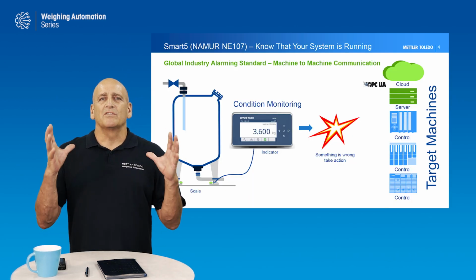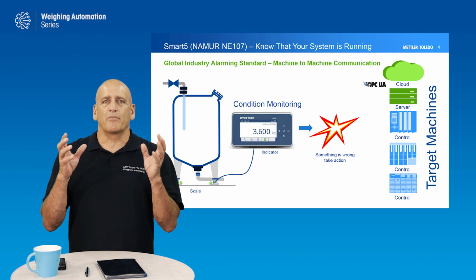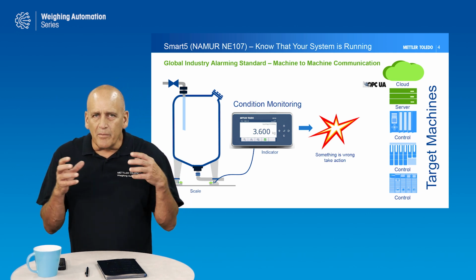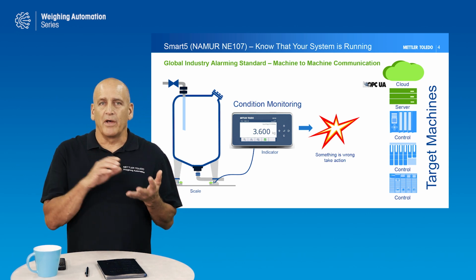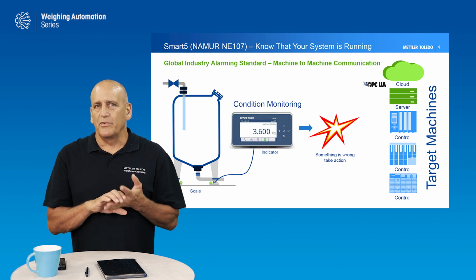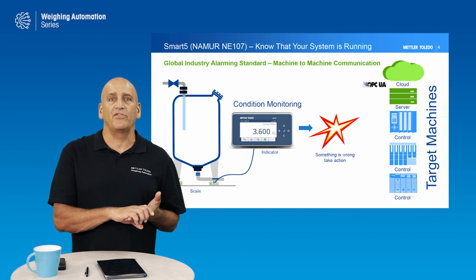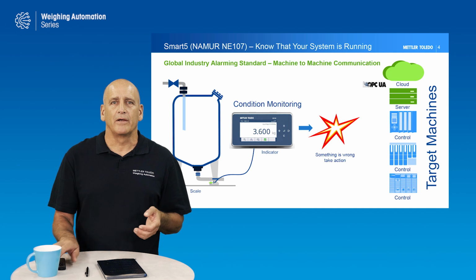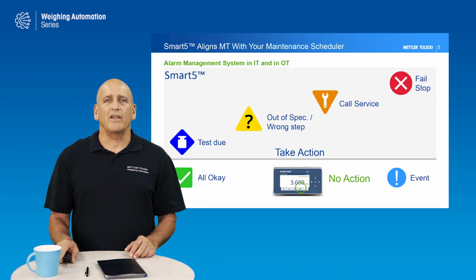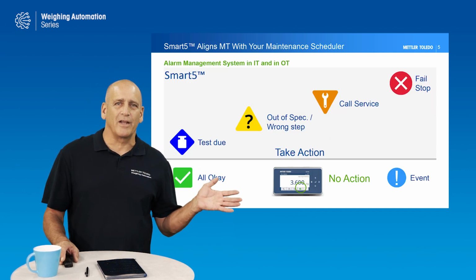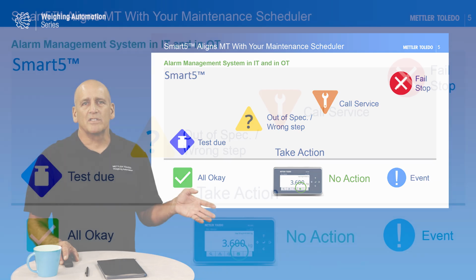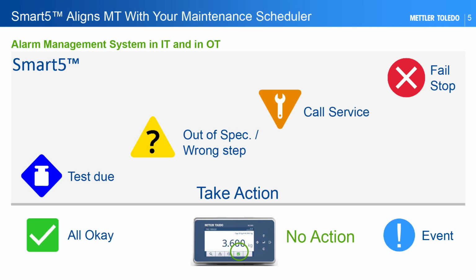Smart5, what it does is when you have a problem with your scale or you have a problem with your sensor, it basically communicates that to another machine, such as a PLC, to a DCS, or to your IT system over OPC UA. In Smart5, it has 5 levels. Naturally, that's where the name comes from. The green level is if everything is okay. If you need a routine test or a calibration, it turns blue. Yellow indicates a process misstep or something that's wrong with the scale.